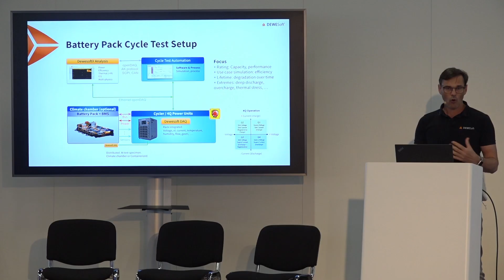So you're cycling to focus on rating, on use case simulation, on lifetime, and also on extremes like deep discharge, overcharging, or thermal stress. This is the pretty common setup where we instrument a battery and measure voltage, current, a lot of temperature channels inside, additionally installed flow, and even gases. So there's a lot to measure in cycling testing.